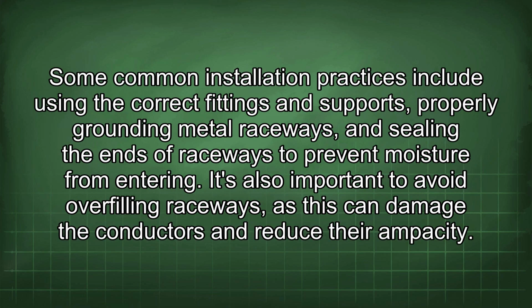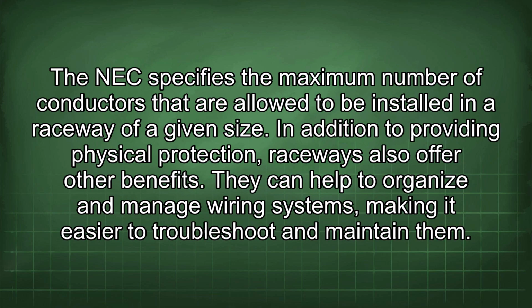Some common installation practices include using the correct fittings and supports, properly grounding metal raceways, and sealing the ends of raceways to prevent moisture from entering. It's also important to avoid overfilling raceways, as this can damage the conductors and reduce their ampacity. The NEC specifies the maximum number of conductors that are allowed to be installed in a raceway of a given size. In addition to providing physical protection, raceways also offer other benefits.